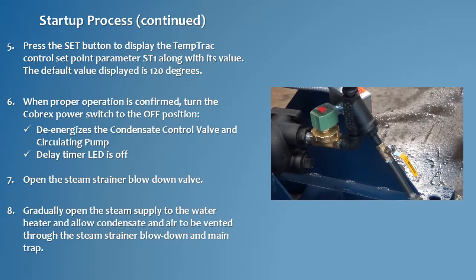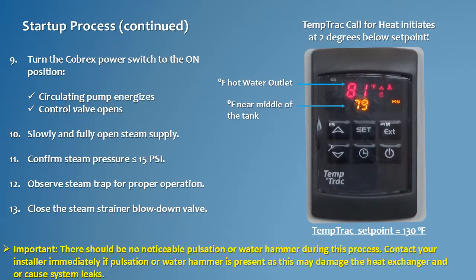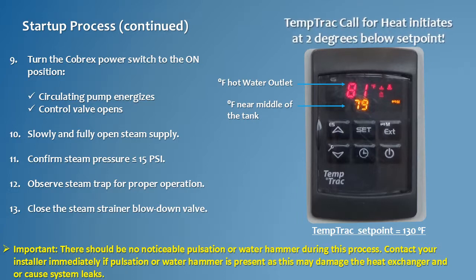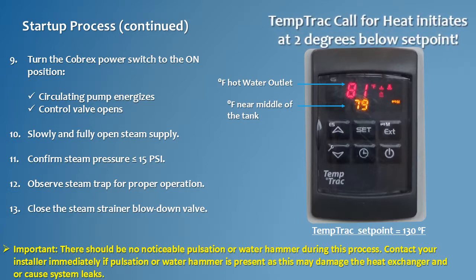Now gradually open the steam supply to the water heater and allow condensate and air to be vented through the steam strainer blowdown and main trap. Turn the power switch to the on position. If the temperature sensed in the tank is 2 degrees or more below the TempTrac set point, the circulating pump will energize and the condensate control valve will open. Slowly and fully open the steam supply valve and begin heating the water in the storage tank.